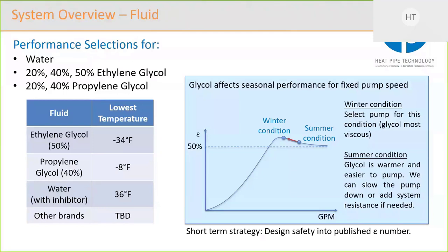So we designed for the winter conditions. So we make sure that we have the right gallons per minute in the system for the winter condition. And the reason for that is that's when the glycol is most viscous and most difficult to pump. So in the summer, when it's easier to pump, if you ran your pump at full speed and you had your control valves wide open, you would actually be operating on a condition further right, and that's where the performance could drop off a little bit. And that's one of the reasons that we have two inline valves, is that we can actually manipulate the system curve for our pump system based on how the conditions change. As I said, the water temperature changes significantly between summer and winter, and we need a system that can behave dynamically towards that.